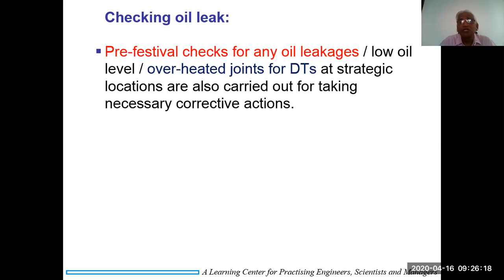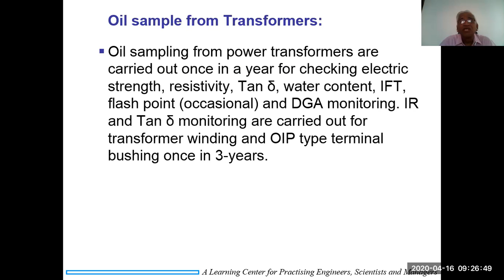Oil samples from transformers. Oil samples from power transformers are collected once in a year for checking electric strength, resistivity, tan delta, water content, IFT, flash point, and occasional DGA monitoring. IR and tan delta monitoring are also carried out for transformer windings and OIP terminal bushing once in 3 years.